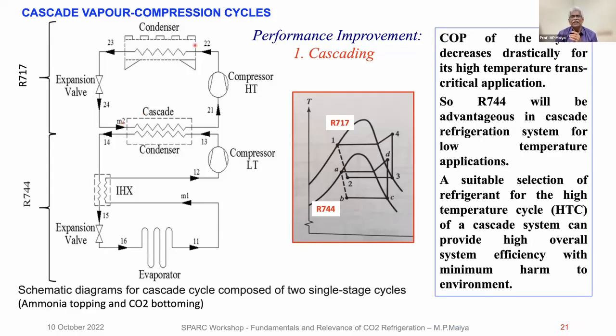First is cascading. If ambient temperature is 40 degrees centigrade and I want minus 30 degrees centigrade in the evaporator, don't use carbon dioxide as a single gas. Use carbon dioxide as the bottoming cycle, and the top cycle is R717 ammonia, with a condensation temperature of 45 degrees centigrade. It evaporates at say minus 10, picking up heat from the condenser of the CO2, and you get minus 35 here. In that way, carbon dioxide is restricted to subcritical operation.